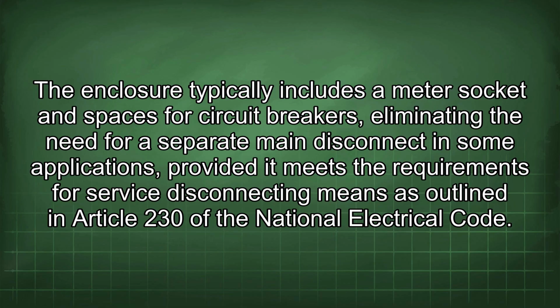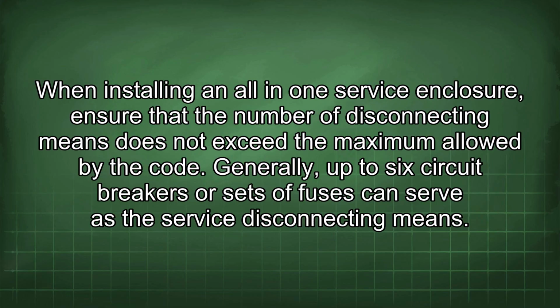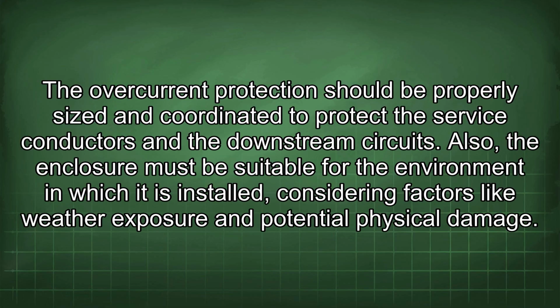The enclosure typically includes a meter socket and spaces for circuit breakers, eliminating the need for separate main disconnect in some applications, provided it meets the requirements for service disconnecting means as outlined in Article 230 of the National Electrical Code. When installing an all-in-one service enclosure, ensure that the number of disconnecting means does not exceed the maximum allowed by the code. Generally, up to 6 circuit breakers or sets of fuses can serve as the service disconnecting means. The overcurrent protection should be properly sized and coordinated to protect the service conductors and the downstream circuits.